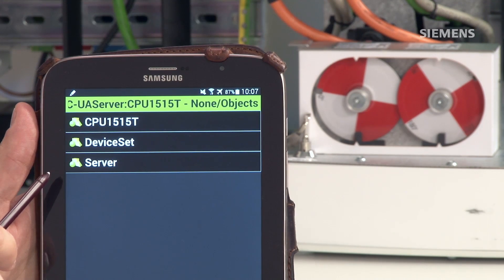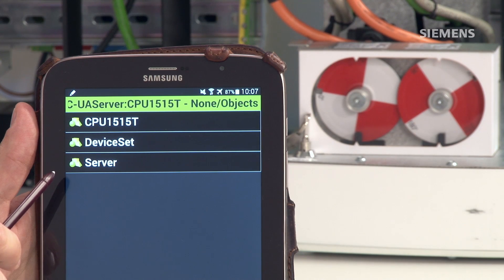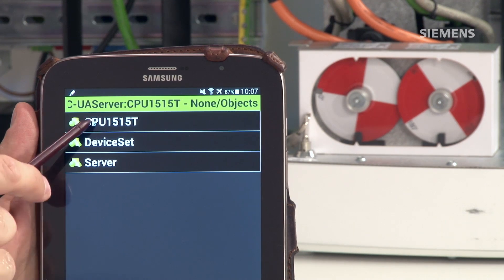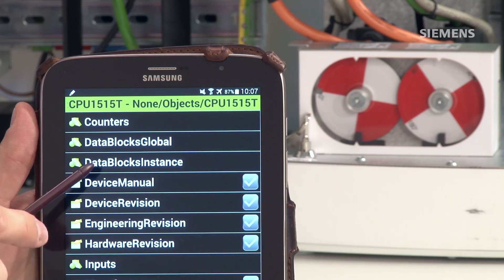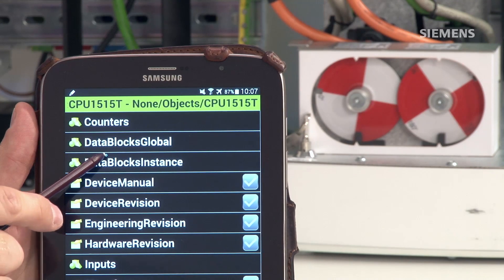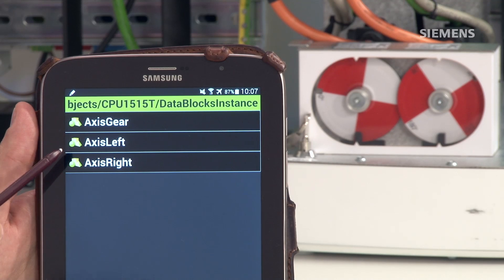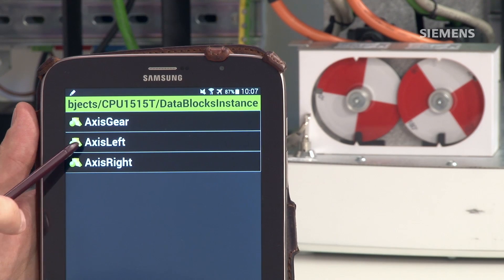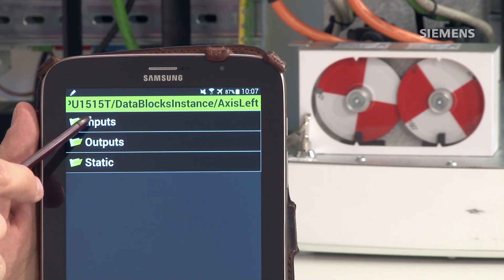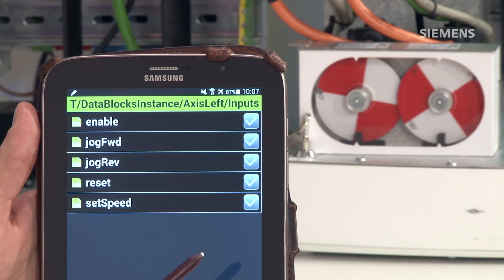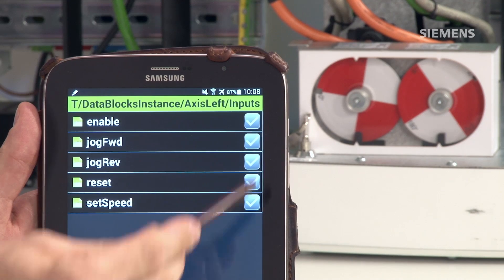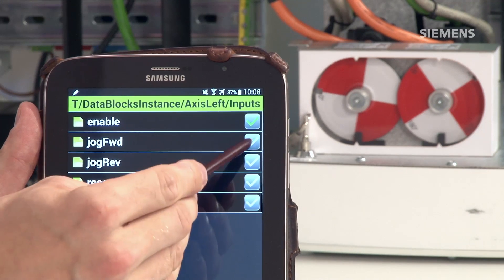I can browse through the variables, at least those that are made accessible via OPC UA. Here's where I locate the CPU and navigate to the Instance Data blocks. I find the Instance Data block for the left axis and here are the input parameters. I'm mostly interested in Enable because I have to switch on the Frequency Converter and jog forward in order to start the axis.